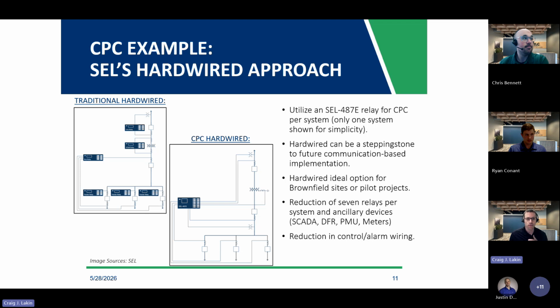The other key to note here is that this is only showing one system, and on most bulk power or bulk electric system designs, you're going to have a fully redundant system. And even at the distribution level now, we're seeing a lot more focus on having redundant systems. That's mostly due to supporting outages. You can take a relay down and not have to transfer customers over to an adjacent substation or an adjacent line that maybe can't handle that extra capacity for the short duration. So again, fully redundant systems is definitely the norm now. And so if it's a reduction of 7 relays per system, it's really a reduction of 14 relays total.